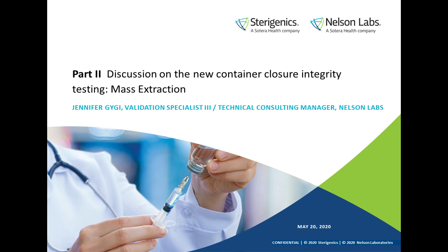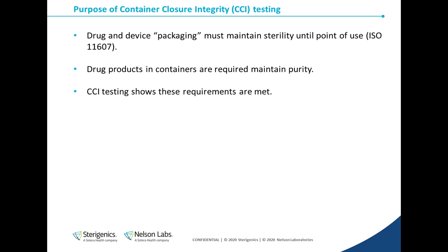I'll be speaking more extensively in that seminar on container closure integrity testing overall and going through all the available testing options. But today, due to time constraints, we're only going to be talking about mass extraction, which is one of 3 container closure integrity tests that we perform here. Mass extraction is a CCI test, or a container closure integrity test. These are tests that are designed for rigid containers, such as vials and syringes and bottles, and CCI tests are used in place of traditional sterility type tests as part of a stability test program to show that these containers are sterile and that they'll remain sterile through the expected use life.